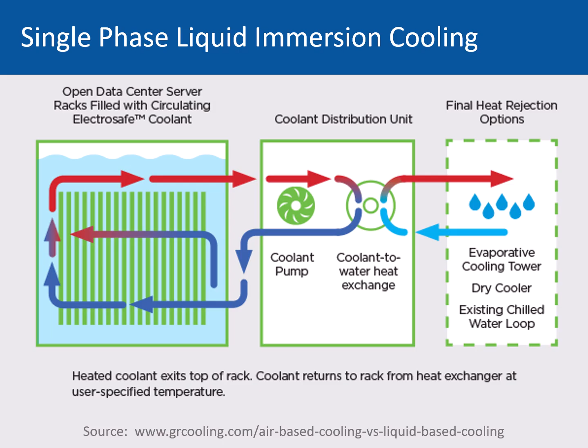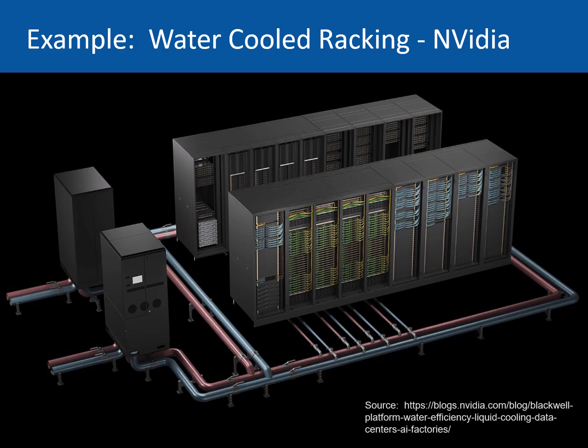Here's an illustration, a photo of a liquid-cooled chip motherboard, and the racking systems where you have water distributed to the racks. Basically, you'll have process water like an industrial plant, and then that water - whether it's chilled water or, I'd contend, just free cooling ambient water - doesn't have to be 40 degrees. It could be 70, 80 degree water depending on the application. Then they have a little heat exchanger inside the rack, which distributes a closed circuit with these little dripless disconnects.